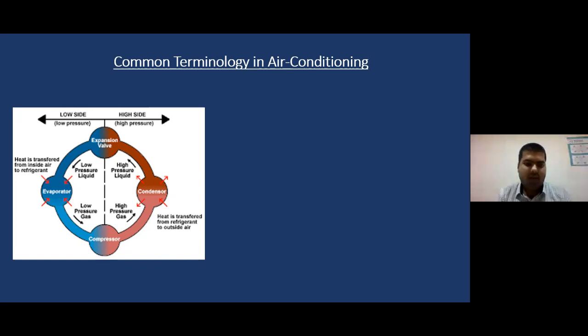So a basic cycle is: my compressor pumps the high pressure gas to the condenser, then the condenser gives a high pressure liquid to the expansion valve. The expansion valve may be a capillary or an electronic expansion valve. Then it sends the low pressure liquid to the evaporator, where the heat is transferred from the inside air to the refrigerant, thereby ensuring cooling. And in the condenser, at the same time, heat is transferred from the refrigerant to the outside air. So this cycle goes on, and that gives the actual air conditioning comfort to the occupant in the room.